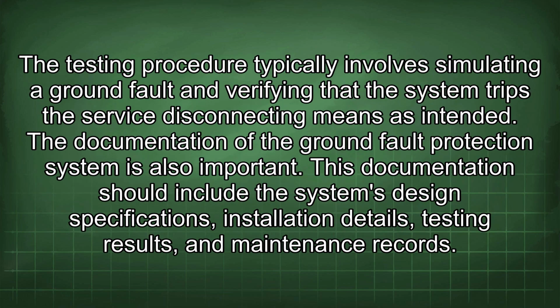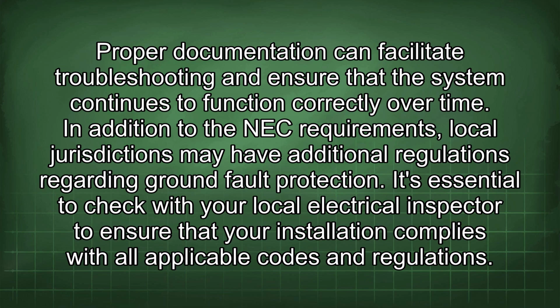The testing procedure typically involves simulating a ground fault and verifying that the system trips the service disconnecting means as intended. The documentation of the ground fault protection system is also important. This documentation should include the system's design specifications, installation details, testing results, and maintenance records. Proper documentation can facilitate troubleshooting and ensure that the system continues to function correctly over time.